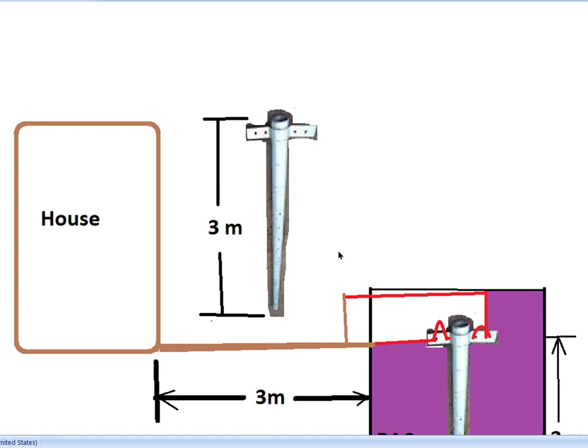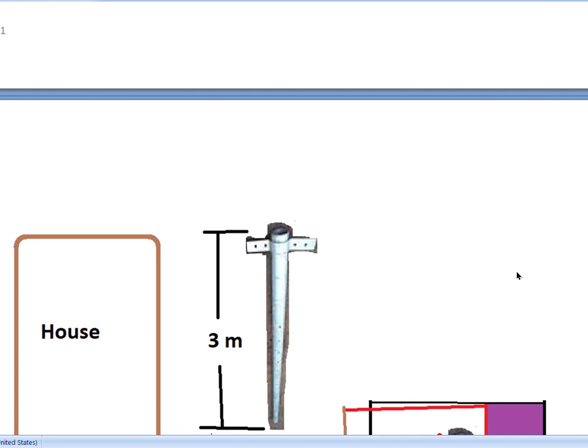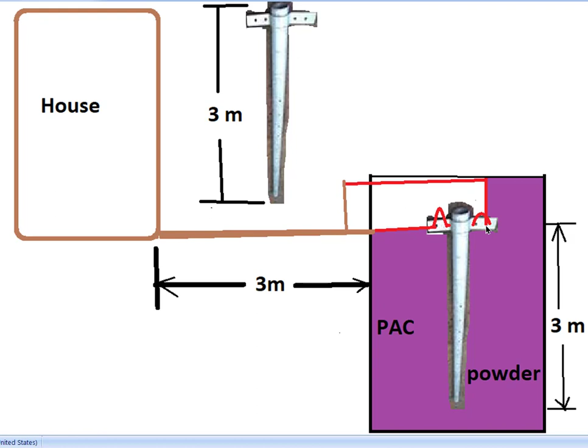Let us say this is the house. From the house, earth points are brought to this point. From this point, run a wire 3 meters in length from here to here. Then dig a pit which is more than 3 meters deep. Put the GI rod in, keep it at the center, then pour the PAC powder mixed with water until the rod is also covered. From the rod, this is one copper wire and this is another copper wire. These two are brought out and connected together, and that joint point is connected to the wire coming from the earth points of the house.